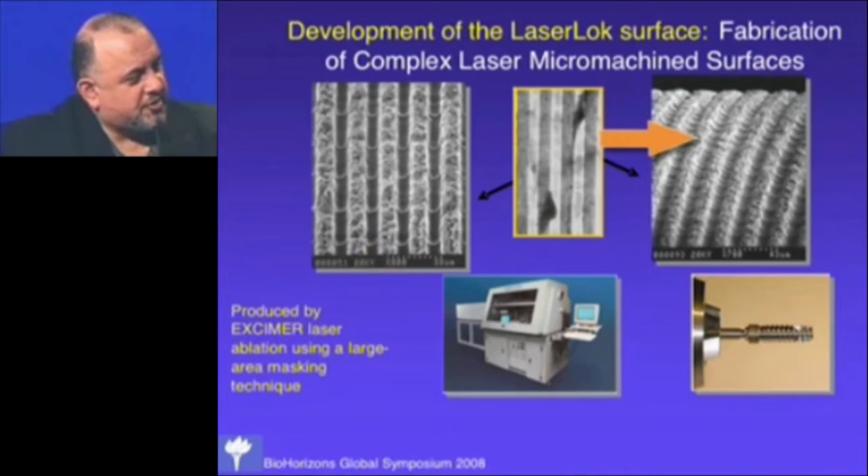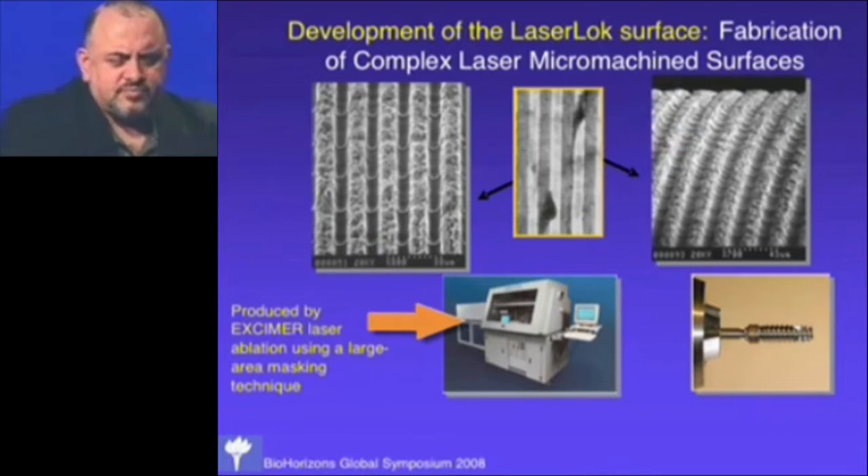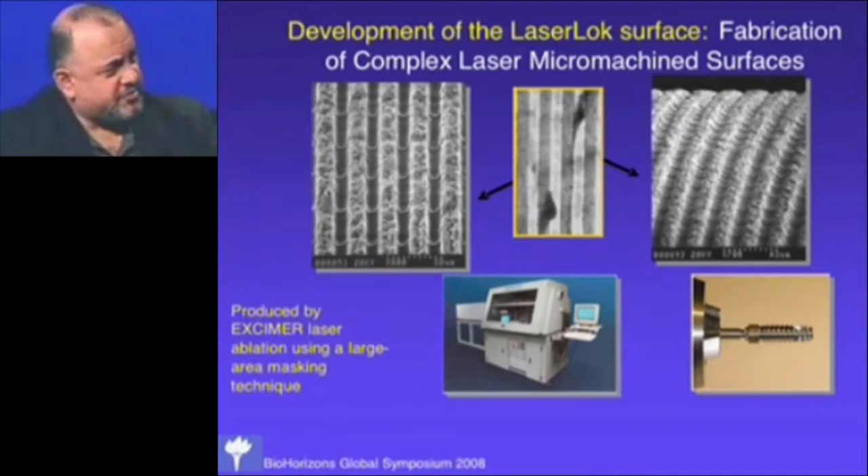These micro-channeled surfaces made in culture turned into micro-channels on a metal surface. This is it on a curved surface — a prototype with a laser micro-machined collar, done using an excimer laser. We've gotten very good at doing these surfaces over the years, and this is the first surface used on the BioLok implants.